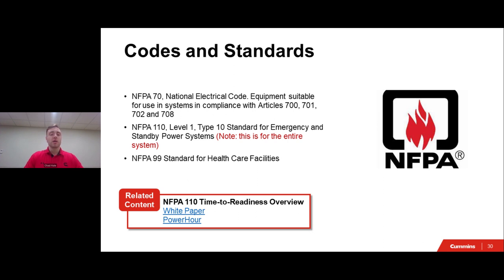It is also important to understand, when it comes to your system, what type and class your system is according to NFPA 110, because this could affect the starting requirements of your system and when acceptable power needs to be at the load side of the transfer switch. So that could be like a type 10, type 60, things like that.